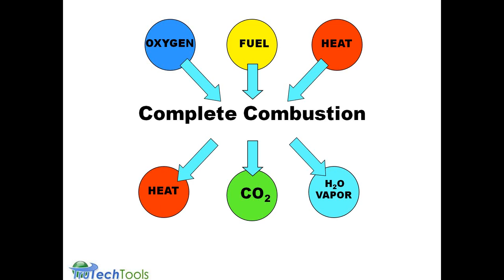Here's a quick overview of what combustion is. You have three things necessary. You have oxygen, fuel, and a source of ignition or heat to create the combustion process. If you have oxygen, fuel, and heat in the proper proportions, you'll get complete combustion, and you'll result in more heat output, carbon dioxide, not carbon monoxide, but carbon dioxide being produced, and water vapor. And this is if everything was in a perfect world and everything ran perfectly correctly in every part of the combustion system, and there were no changes in available air, fuel, or any types of blockages or problems with the equipment.